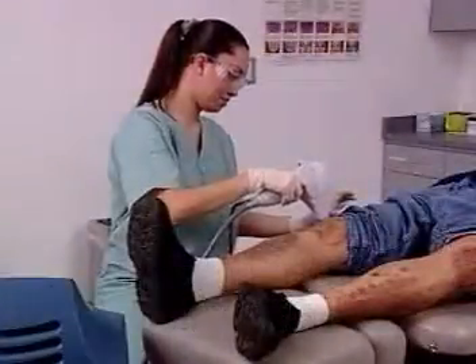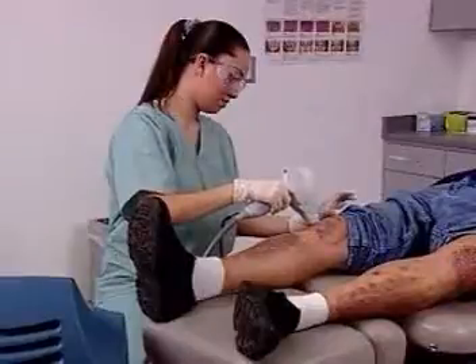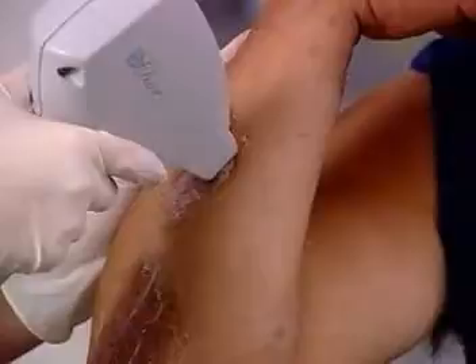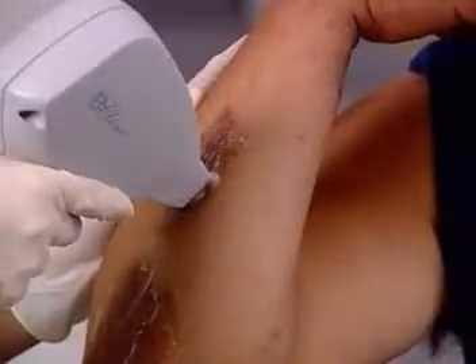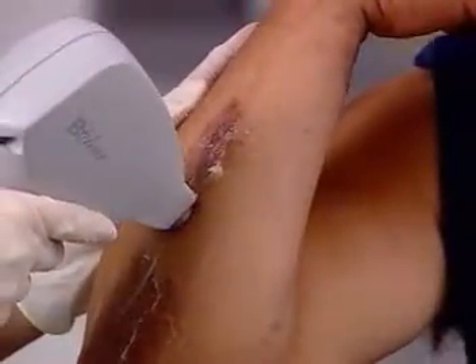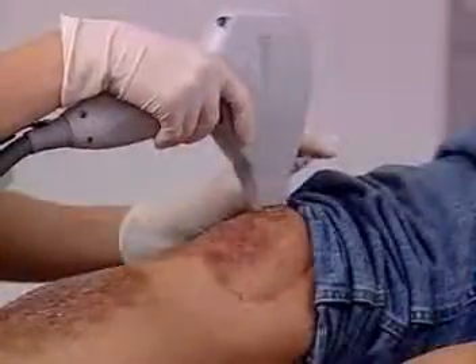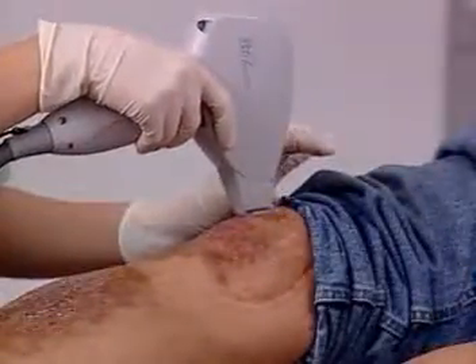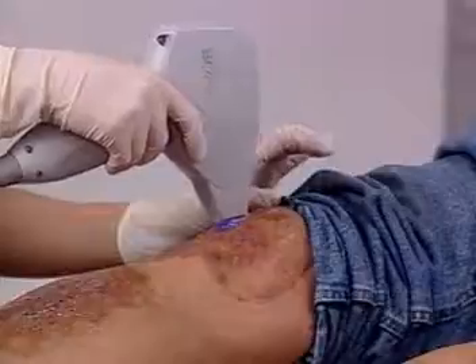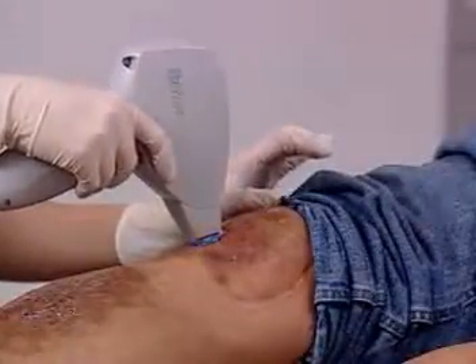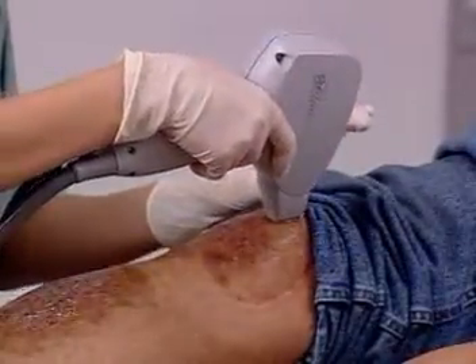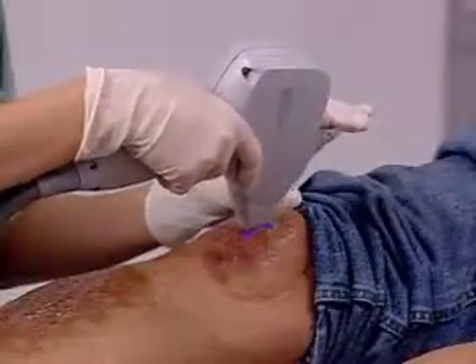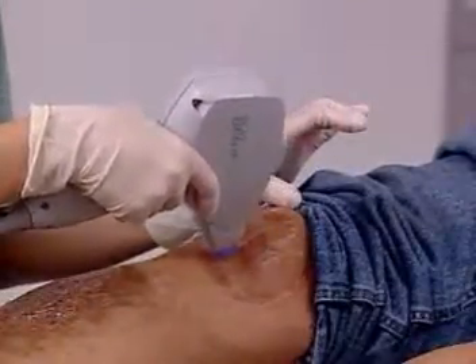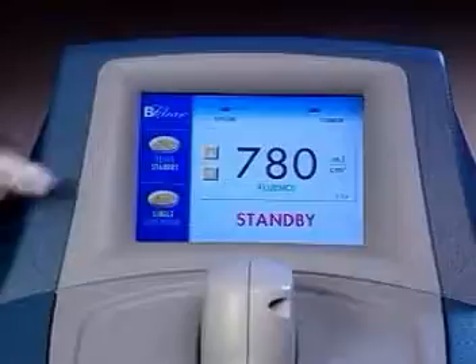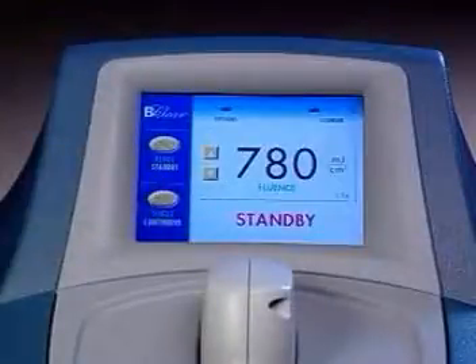Your BeClear system can operate in either single or continuous treatment modes. In the single treatment mode, the system will deliver the prescribed fluence in a single emission each time the foot switch is pressed. In continuous treatment mode, the system will continuously emit light as long as the foot switch is pressed, delivering the prescribed fluence at a consistent, pre-described rate. Audible beeps provide a cue for moving the handpiece. Use the Mode button to select single or continuous treatment modes.